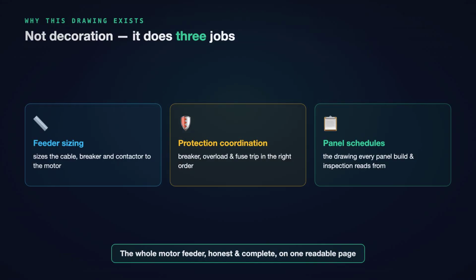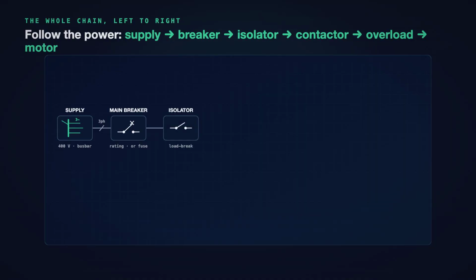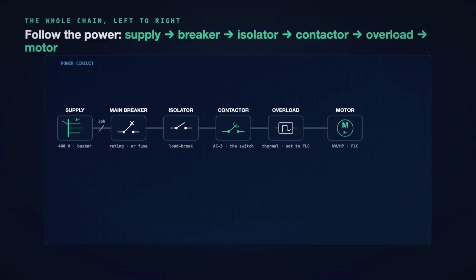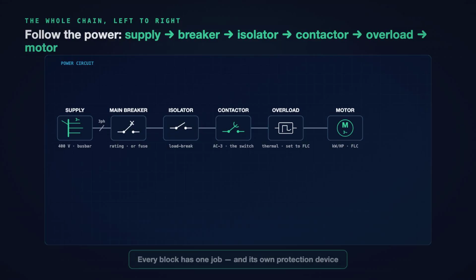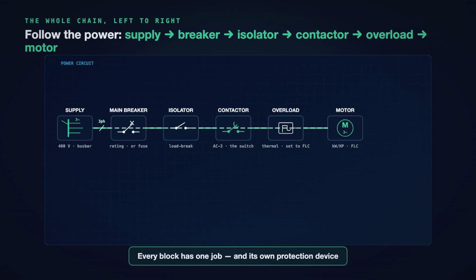Here is the whole chain, left to right, the way the energy travels. It starts at the incoming supply, the bus bar the feeder taps off. From there it runs into a main breaker or a fuse switch for short circuit protection. Then through a line isolator, a switch you can lock off. Into the contactor, the switch that actually starts and stops the motor. Then the overload relay, guarding the windings. And finally the motor itself. Every block on that line has one job, and its own protection or control device. Learn the chain, and the whole diagram opens up. Let's take it one block at a time.